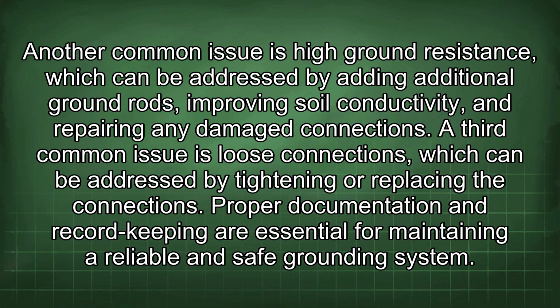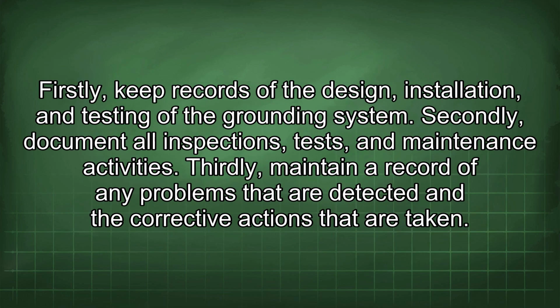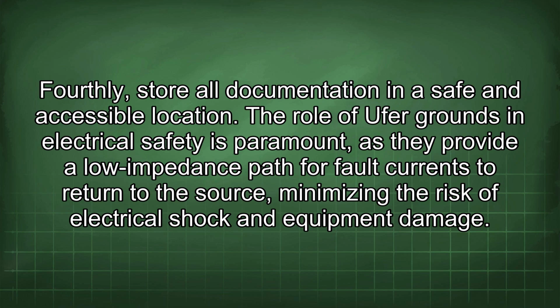A third common issue is loose connections, which can be addressed by tightening or replacing the connections. Proper documentation and record keeping are essential for maintaining a reliable and safe grounding system. Firstly, keep records of the design, installation, and testing of the grounding system. Secondly, document all inspections, tests, and maintenance activities. Thirdly, maintain a record of any problems that are detected and the corrective actions that are taken. Fourthly, store all documentation in a safe and accessible location.